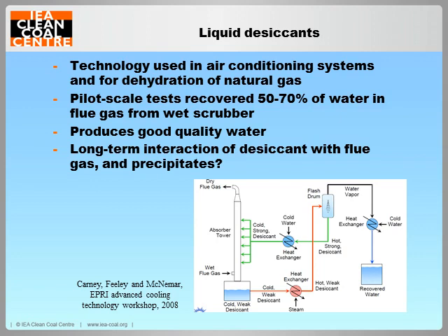The process involves cooling the flue gas before it enters an absorption tower into which a liquid desiccant is sprayed. The wet desiccant is then heated before it is sent to the regenerator. The reason for this is that the hotter the desiccant, the easier it is to separate the water. The resultant water vapour is then condensed. The regenerated desiccant is filtered and cooled before being injected back into the absorption tower. The recovered water had a similar quality to that from reverse osmosis treatment, which is normally used to produce boiler make-up water.